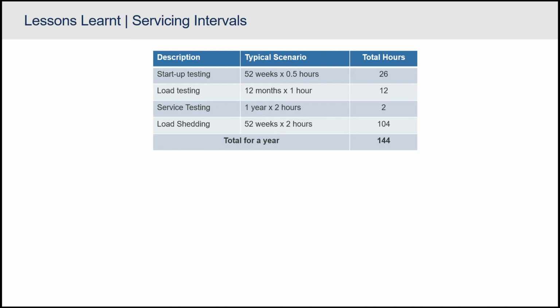As part of the service, they normally run it for about 2 hours. There's a lot of load shedding at certain points, but also points with no load shedding, so let's average it out and say there's one load shedding event every week of the year. If we add all of that together, it comes to about half of the 250 hours, about 144 hours in a year. So even being relatively conservative, you'll rarely find generators running more than 250 hours in a year.